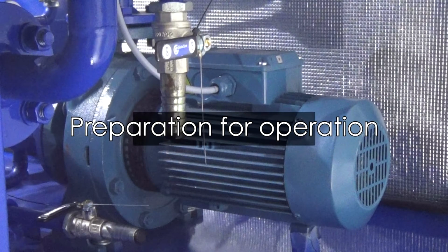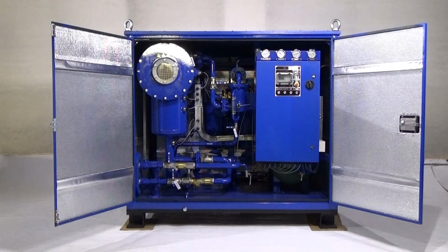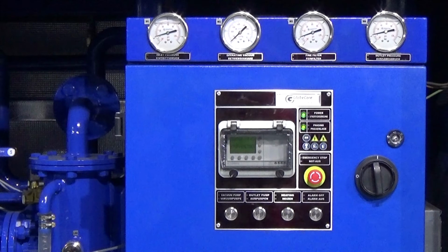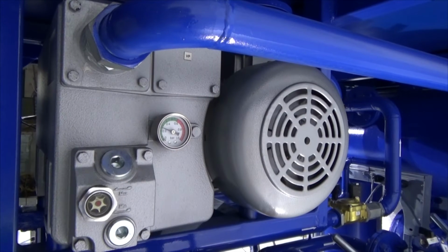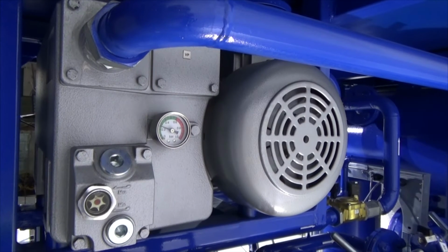vacuum. Preparation for operation. The unit must be sufficiently lit and installed on a flat horizontal surface so as to ensure unobstructed access to the controls. Ground the unit by connecting the grounding device with the unit's grounding bolt with a copper wire. Check that all valves are shut. The emergency stop button on the control cabinet must be released. Check oil level in the vacuum pump. If necessary, add vacuum oil.